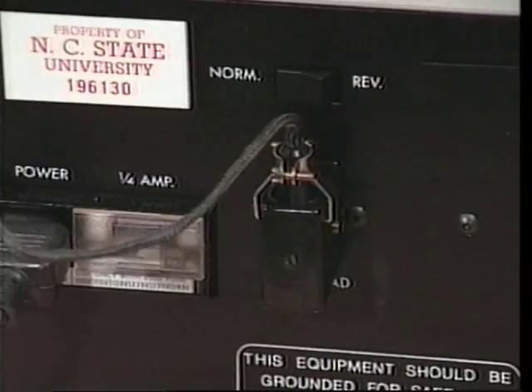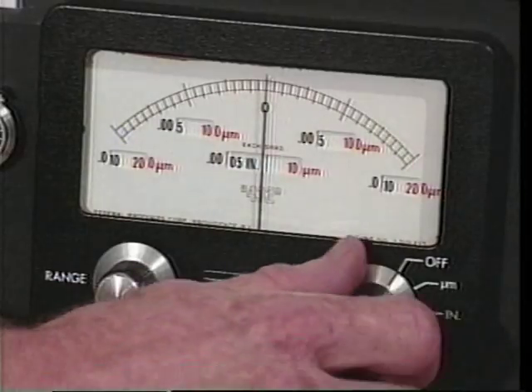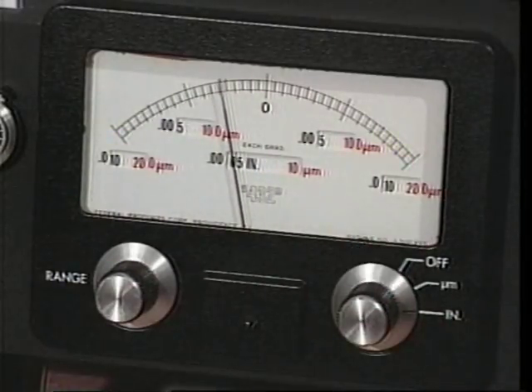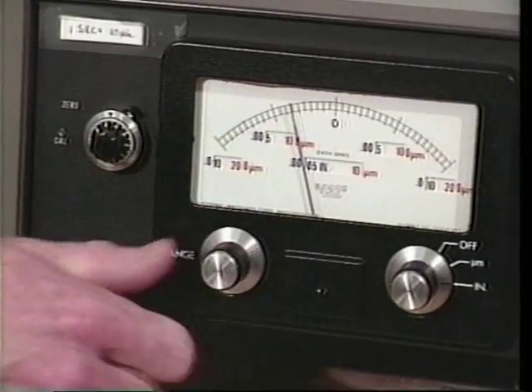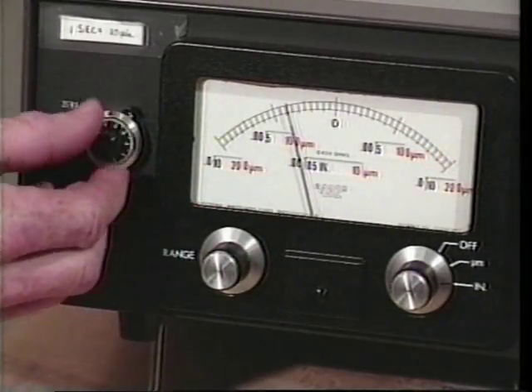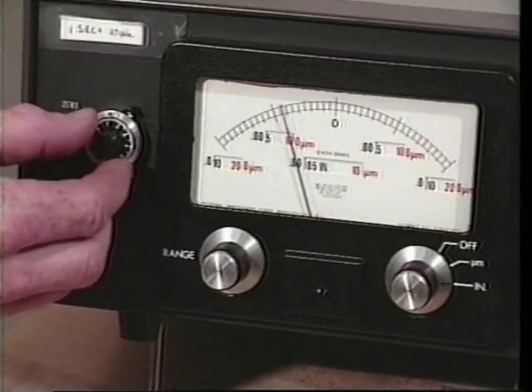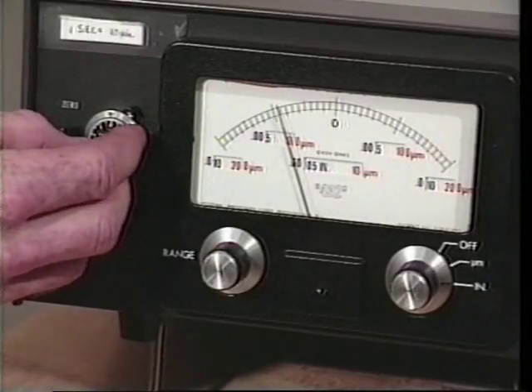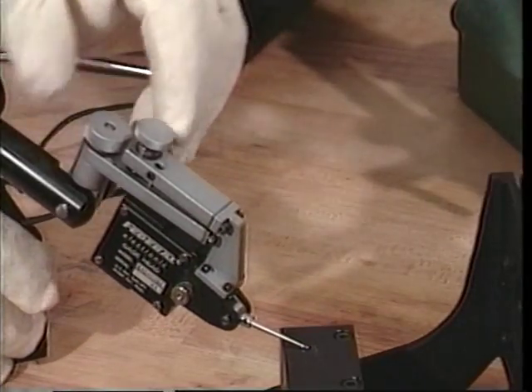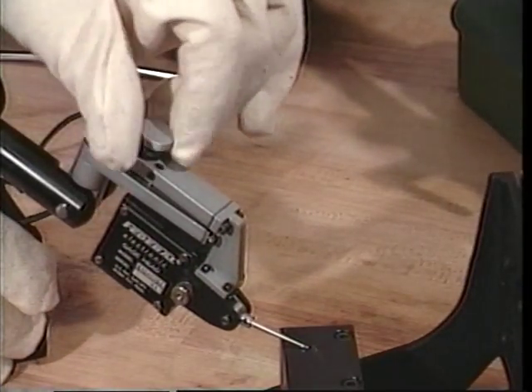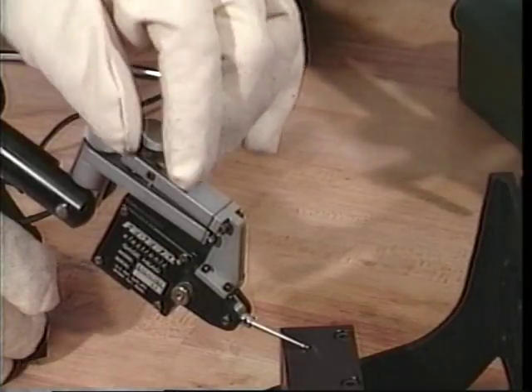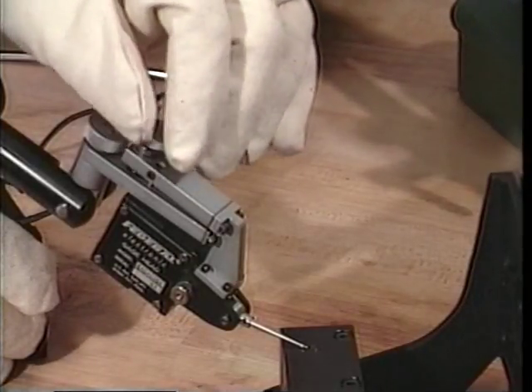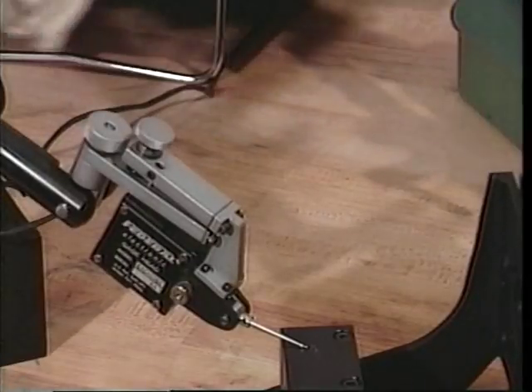Verify that the stylus unit's cable has been connected to the rear of the console. Power up the console and allow time for electronic stabilization. After warm-up, select the range with the largest measurement spread. Position the electronic fine adjust knob in the middle of its range, that is, at 0, 0. Using a sturdy mounting fixture, carefully bring the stylus into contact with the measurement surface so that the display needle remains on scale. Using the mechanical coarse adjust knob, position the stylus such that the display needle indicates 0.